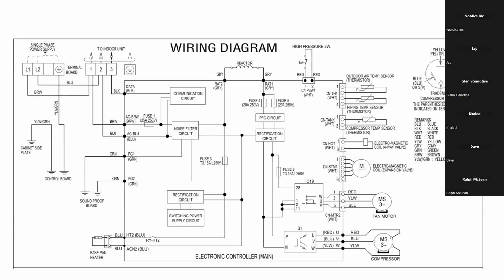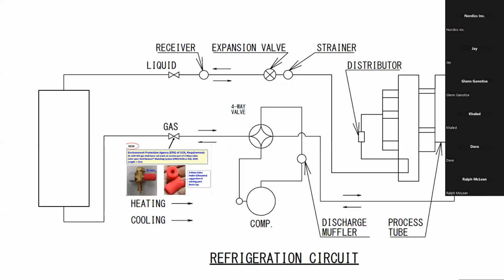On the wiring diagram, it's almost the same for the outdoor unit, except that it has a base pan heater now. So this is the new thing that you can see at the bottom left, the base pan heater. The remaining is pretty much the same. Did not change. Now with the new refrigerant, we have a cap, which is a red cap, which is mandatory. So this brass cap has been replaced with this red cap. And when you see a red cap, that means for sure it's R-32 refrigerant inside.